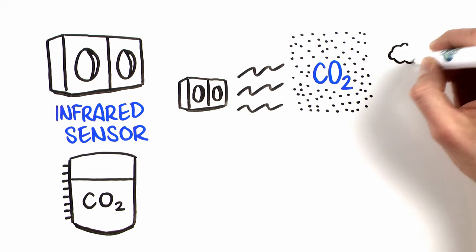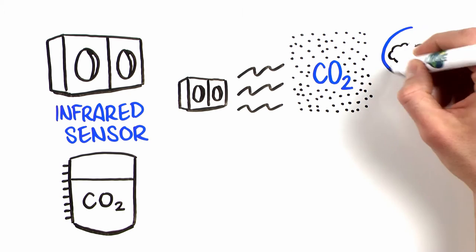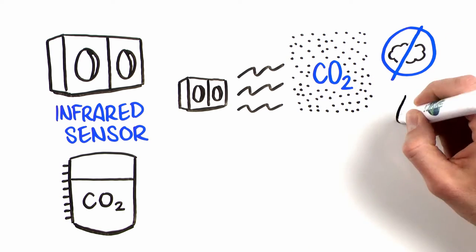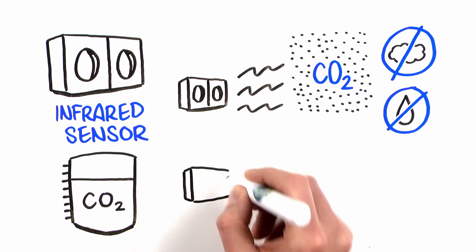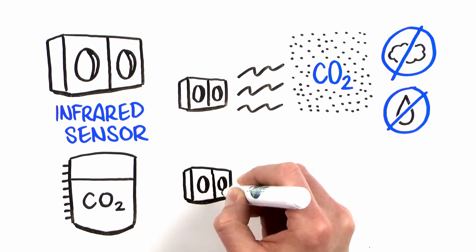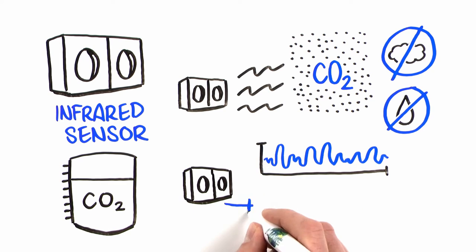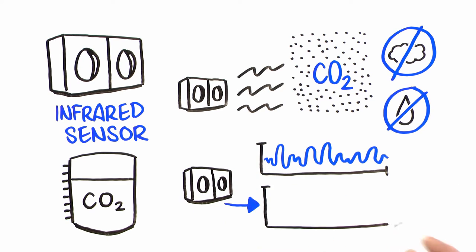An auto-adjusting linearization process allows the IR sensor to adjust for stable output, minimizing drift and requiring less frequent calibrations.